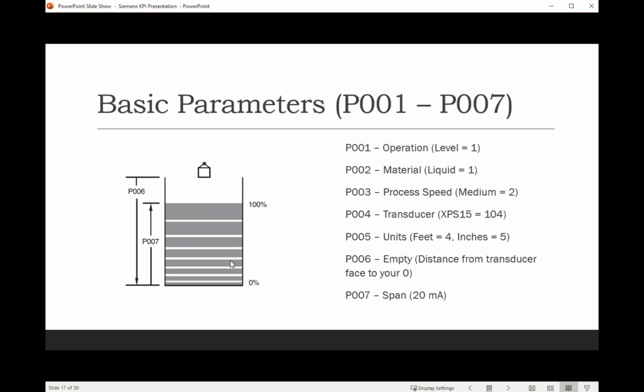With the standard Hydroranger 200, the one that uses the push-button remote, everybody knows it as P001 through P007. So this one is parameter-driven. You've got to pull up the manual and look up your quick start and see what P001 and P007 mean. So for example, you're always going to have to answer what operation. Are you doing level, are you doing distance, or are you doing space? Most common with us is we're going to be doing a level application. So you take your handheld remote, put a 1 in there, and then move on to number 2, which is material. Are you doing liquid, or are you doing a solid?